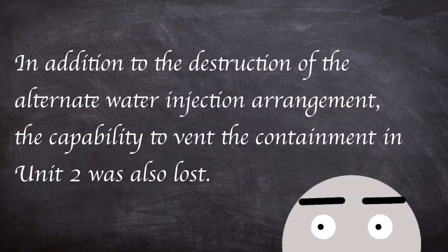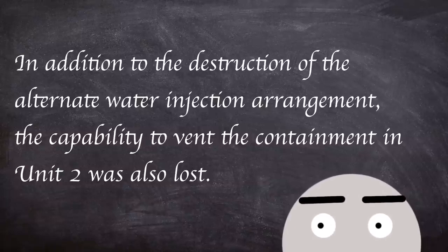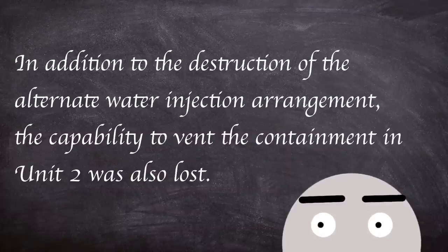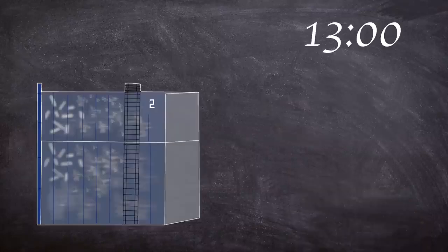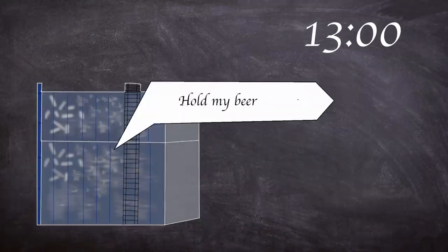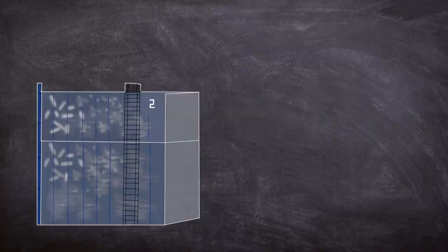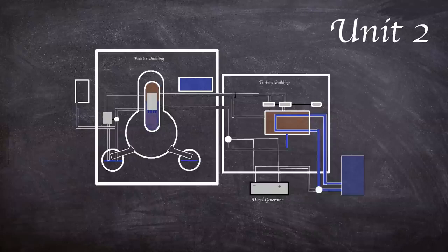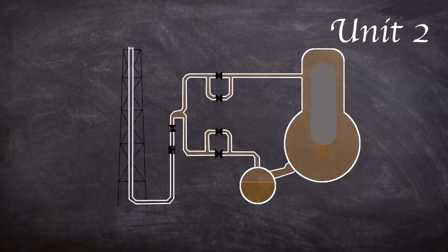In addition to destruction of the alternate water injection arrangement, the capability to vent containment in unit 2 was lost. At around 1 pm on the 14th, unit 2 began to experience cooling issues as well. In what seems a repeating theme, reactor pressure increased as cooling water level decreased. To enable low pressure fire truck water pumping, safety valves were operated to drop reactor pressure.